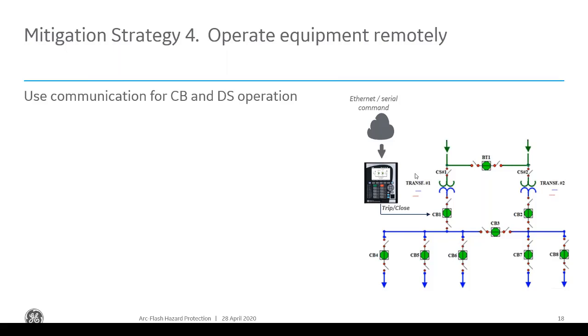Yes, obviously it does. When the switchgear is enclosed and in normal position, obviously all bets are off. If you need to do some sort of maintenance, you need to open that piece of switchgear up, and that bypasses those controls. But strictly when the switchgear is in normal operation, depending on the arc flash energy, it can significantly reduce it. And by reducing the arc flash energy, it can significantly reduce the PPE required to be in front of that switchgear. Obviously, if you're going to open up the switchgear, that goes out the window. But if you're going to open up the switchgear, you're probably going to de-energize it. You're not going to be working on a live piece of switchgear.